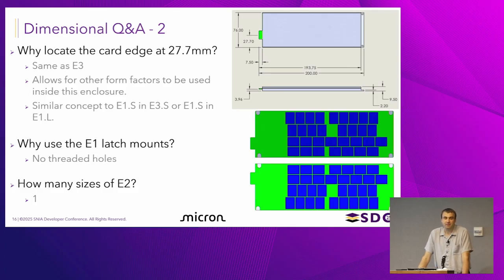There's a certain thermal dissipation where everything breaks. Air cooled doesn't work anymore. One-sided cold plate doesn't work, so I've got to go two-sided. Two-sided may not work, so I've got to go cryo or something ridiculous. Immersion. Dropping the performance of this, you can probably drop the power where it's not that big of a deal. Exactly. And that's TCO at the end of the day.